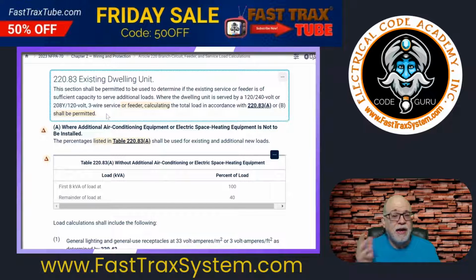Okay, so before I even look at this, a lot of myths that are out there say that you have to use it. You're permitted to do this, but you know what you could do? You could actually recalculate the load again as if you're starting from scratch, take all of the appliances, take all the variables that you would have in normally sizing a service, add in your new loads and do it as if everything is new.